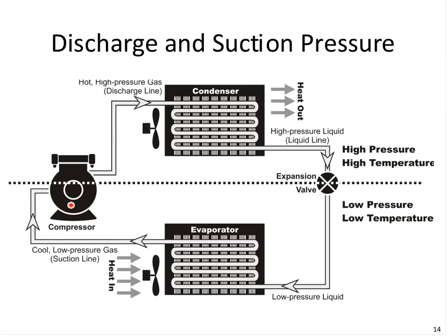We often think of a compressor as pushing, but it's also doing an equivalent amount of work on pulling vapor out of the evaporator. So the high pressure liquid would be introduced to the low pressure side, and as we have air from the refrigerated space come in contact with the heat exchanger, the evaporator, that liquid refrigerant begins to phase change to a vapor, absorbing heat at a temperature that we want. And that temperature can be controlled by adjusting the pressure in this evaporator. The lower the pressure, the lower the temperature.